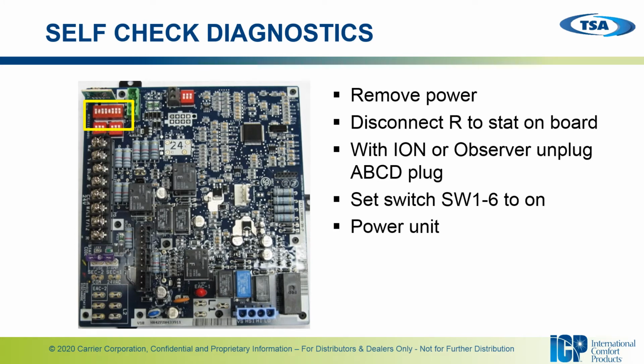With the new FER changes, the furnaces have also had some control board upgrades. On these furnaces with control boards and variable speed motors, they now have a self-check diagnostics feature. To enter this self-check diagnostic mode, you must remove power from the furnace, and disconnect R to the thermostat on the control board. If you're using a communicating unit or thermostat, you must disconnect the 4-pin green connector in the upper left corner of the control board from the thermostat. Once you've done that, you can turn switch bank 1, switch 6 to the on position, and then power the unit up to enter the test mode.